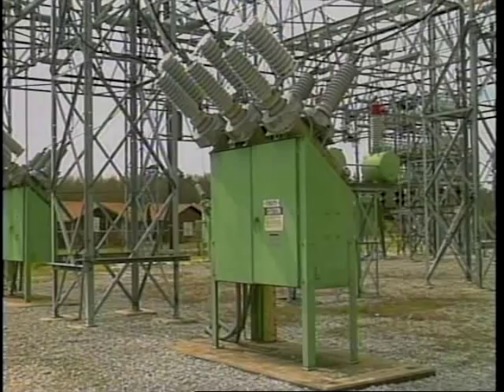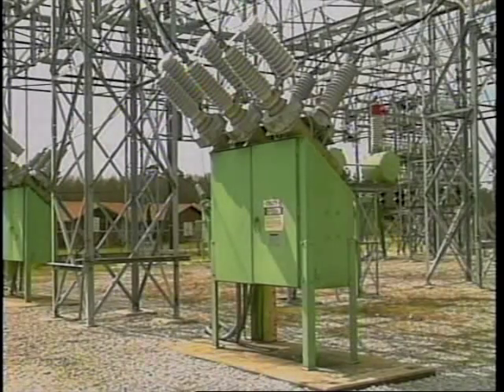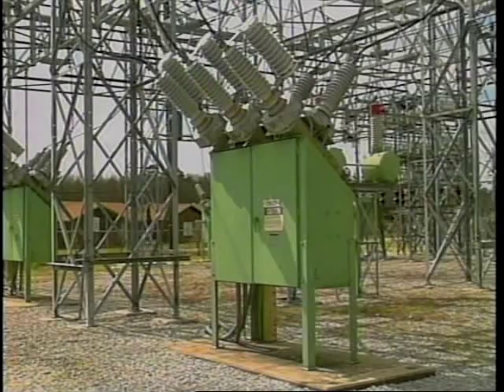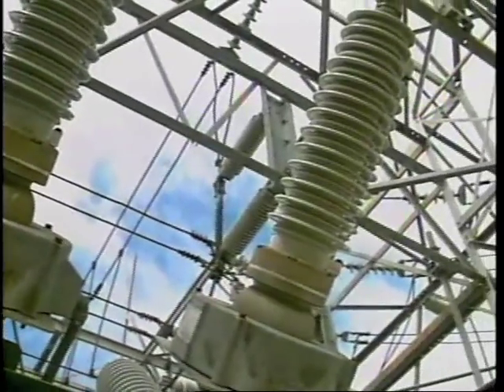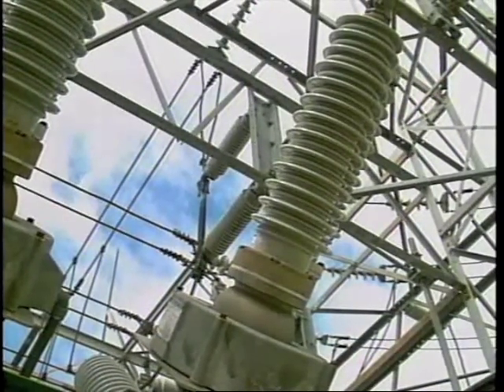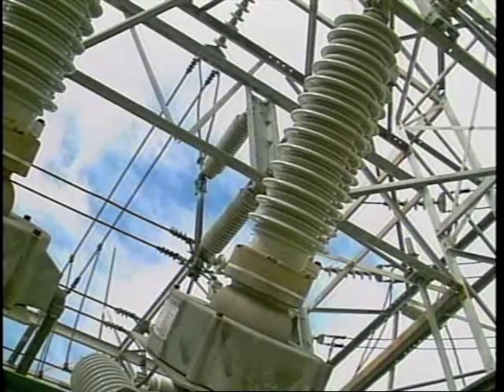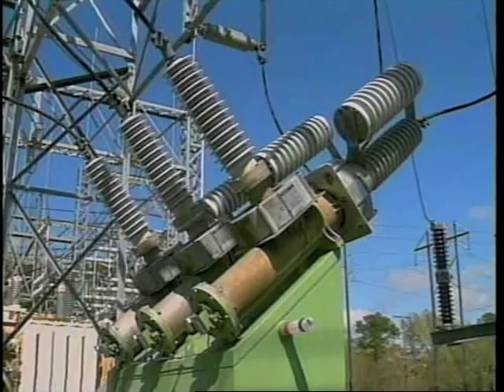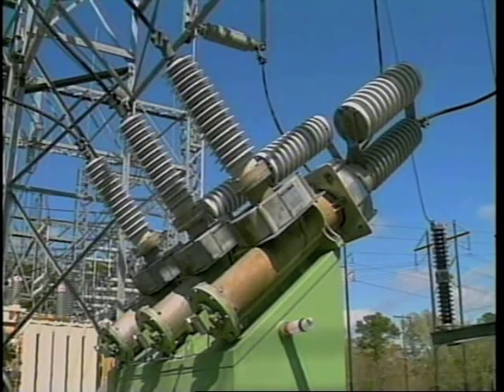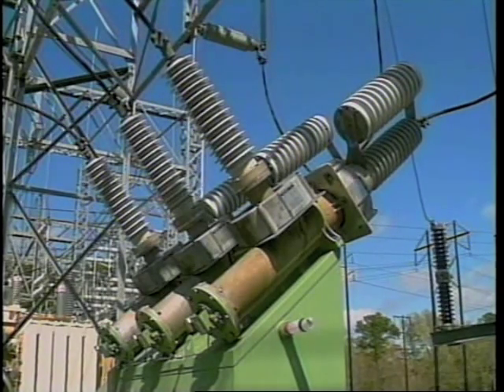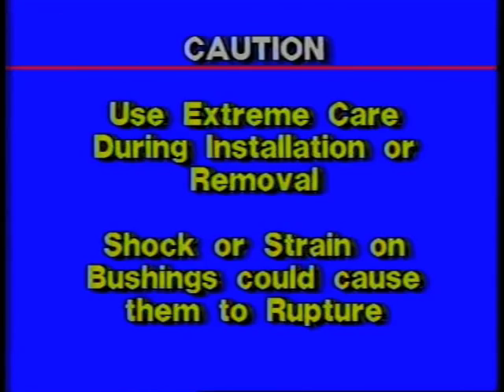The bushings in sulfur hexafluoride circuit breakers are designed with their porcelain center exposed to the main breaker tank, which is filled with SF6 gas. Since the porcelain is under positive pressure, the gas will flow outward in the event of a pinhole crack. This will preserve the insulating qualities of the bushing until repairs can be made. The main purpose of the bushing is to provide an electrical path from the breaker to the connecting bus. Some bushings may be insulated with sulfur hexafluoride gas. If the bushings contain sulfur hexafluoride gas, extreme care must be exercised during installation or removal. Any shock or strain on the bushings could cause them to rupture.